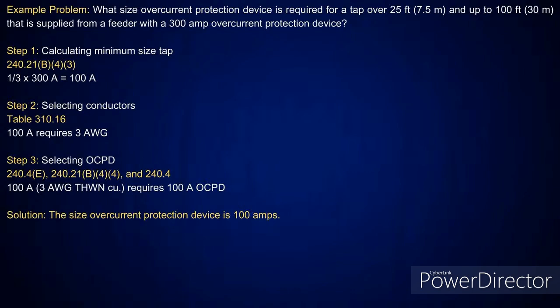All right. This one's a 25-foot to 100-foot tap, and it's supplied from a feeder with a 300 amp overcurrent device. Everything else that's left, over 25 foot, you take at a third. So I'll take the upstream overcurrent device at a third, which was 300 amps, gives me 100 amps. Go to Table 310.16, and looking at the 75-degree C column, the number 3 is good for 100 amps. And then you go look at Table 240.6(A), you have a 100 amp overcurrent device. So your minimum overcurrent device is 100 amps with number 3 conductors.